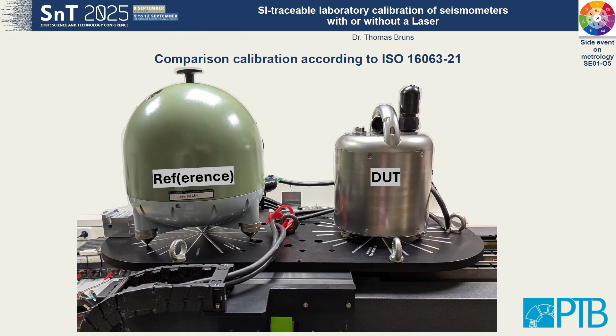There's also a standard out there, ISO 16063, same series, but part 21, which describes the side-by-side calibration for accelerometers. And if you do that, it's pretty simple. The equation is that the sensitivity, here I'm talking about magnitude, but phase works in kind of the same way, of the device under test is simply the sensitivity of the reference rescaled by the ratio of the voltage amplitudes that you measure from the two instruments that you set up side by side. And if you do that, for those two devices that I showed in the photograph before, you get this frequency response curve, which is nice, looks simple, smooth, and wrong.